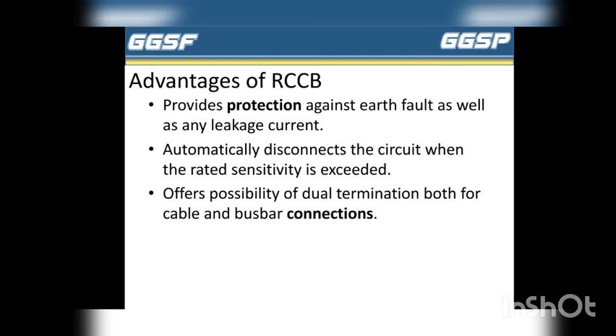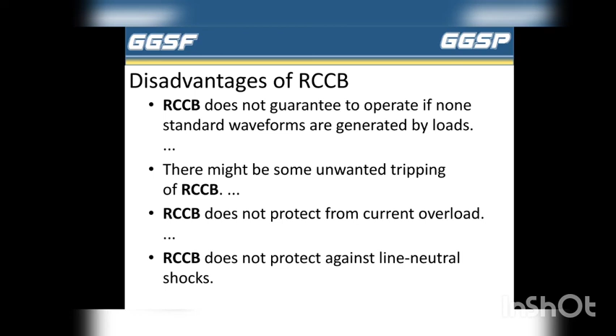Next one is disadvantages of RCCB. First disadvantage is the RCCB does not guarantee to operate if non-standard waveforms are generated by loads. Next, there might be some unwanted tripping of RCCB. RCCB does not protect from current overload. RCCB does not protect against line neutral shocks. This is the RCCB.